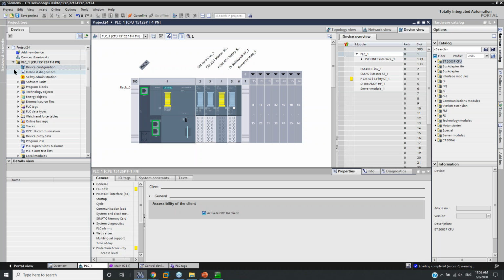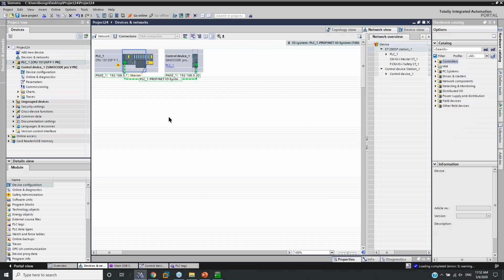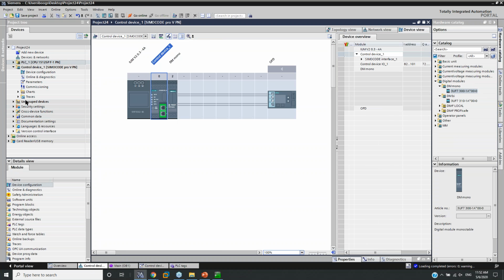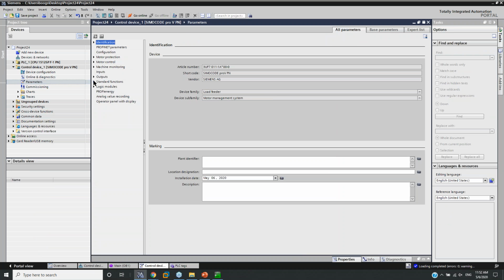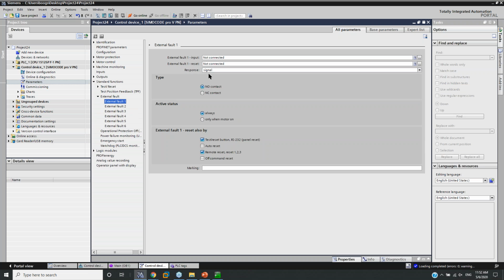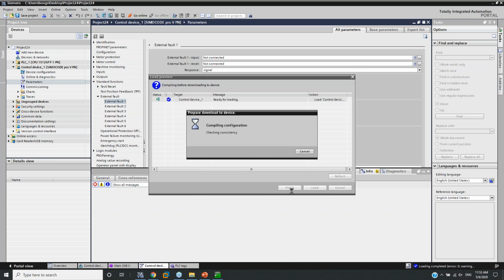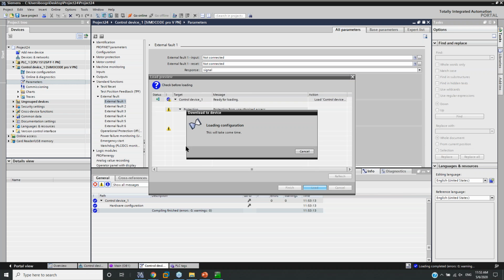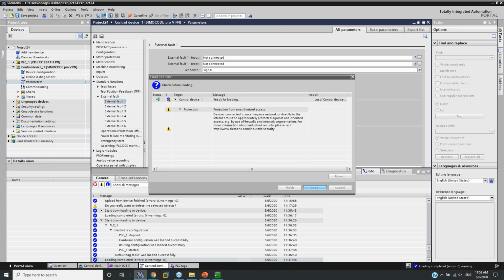Stopping my demo. And let's go to the SIMOCODE. Okay, and we're going to go to parameters. I'm going to pick standard functions and go to external faults. And let's just say, for time constraints, I set this up as an RTD temperature fault. So I'm going to go RTD fault, and I'm going to put it right there in marking. Download that to my SIMOCODE. Hit load. Okay. Let that finish. It just takes a second.